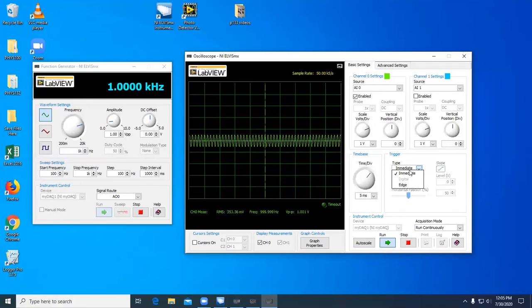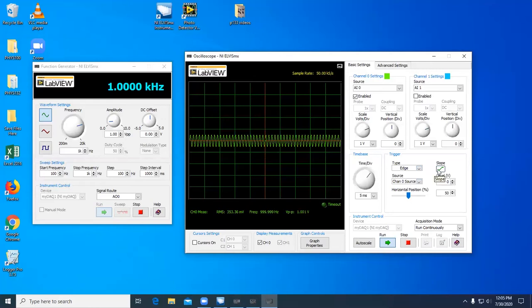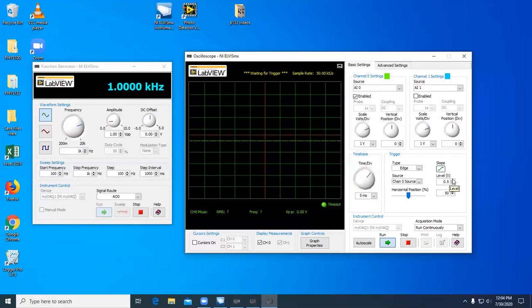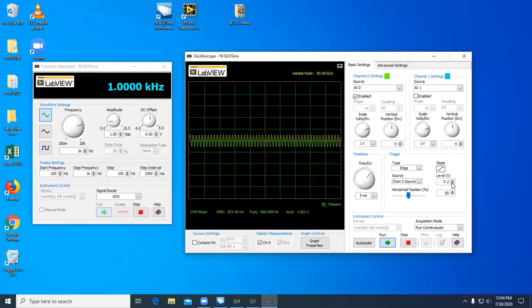If we change the type to edge, we can trigger off of a rising or a falling edge. The oscilloscope looks for an incoming signal that, in this case, is rising at 0 volts. We can change the level of the trigger, and as we do, you will notice that the red line moves up. It's gone higher than the level of our signal, and so therefore it can't find an edge to trigger off of anymore. The red line always has to be within the waveform.